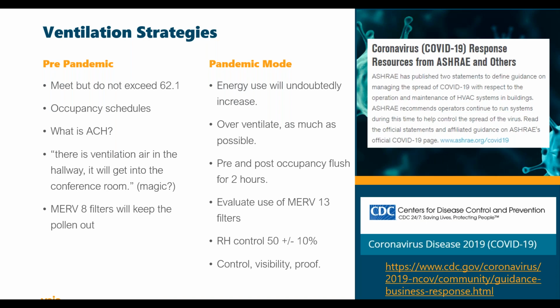More outdoor air for longer periods of time is going to max out the cooling equipment this summer and tax the heating plants this winter. Fan energy is going to increase as we stack up higher MERV filters in our air handlers and add UV lighting banks. If those fans are on VFDs, we're not going to see the modulation - we're going to see a lot of fans running at 60 hertz or more to try to make these buildings, quote, safe for occupants going forward to help meet these guidelines.